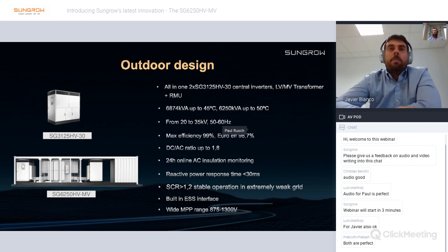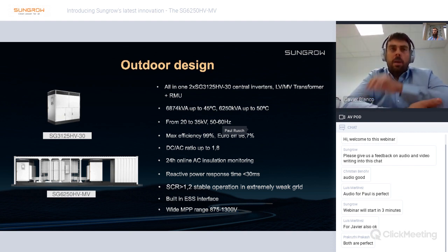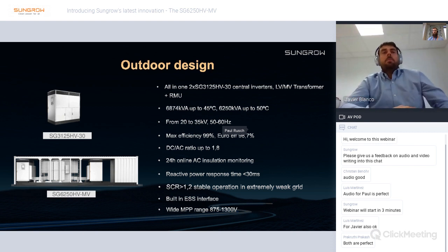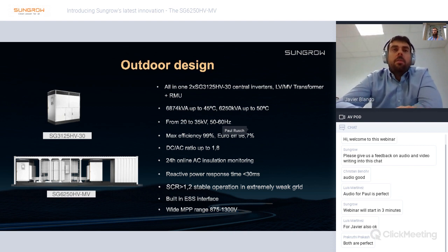Talking about grid frequency, the maximum efficiency of the central inverters is 99%, with a Euro efficiency of 98.7%. One of the important features of this MV station is that we can manage a DC-AC ratio up to 1.8, which is relevant in many countries where this utility solution is being deployed in the future. There is also 24-hour online AC insulation monitoring.